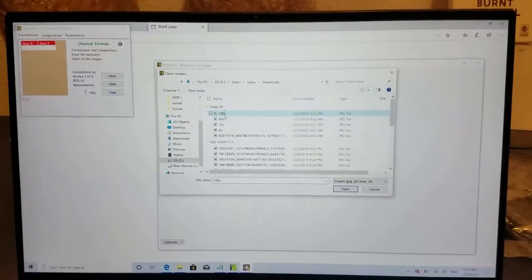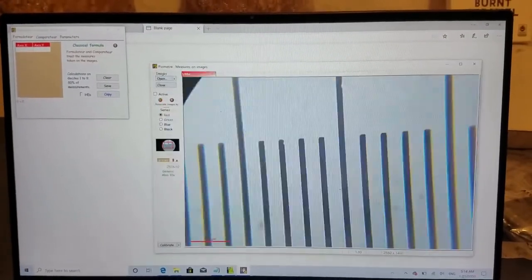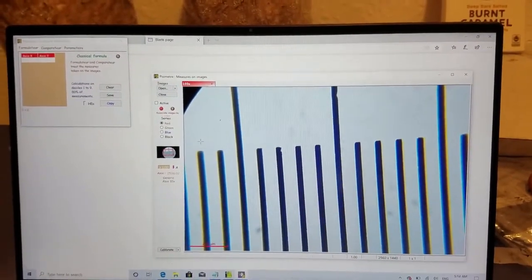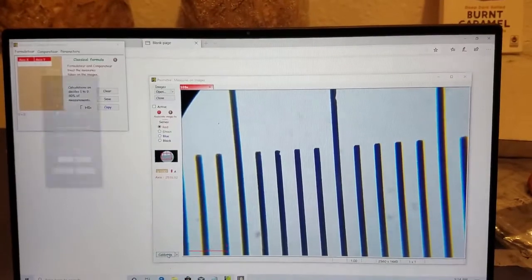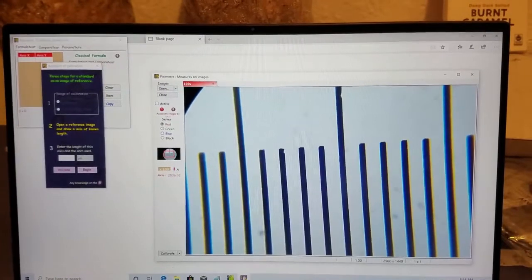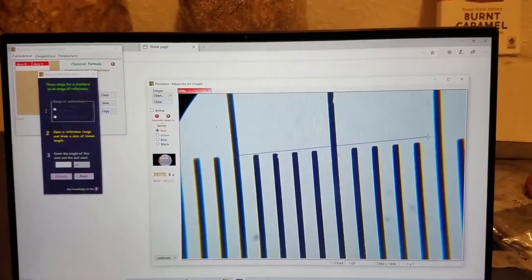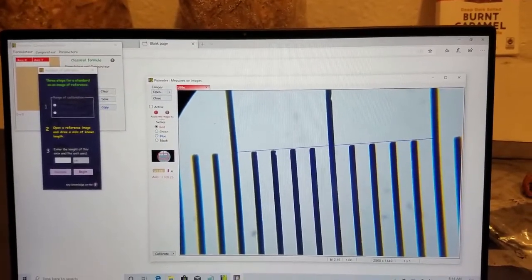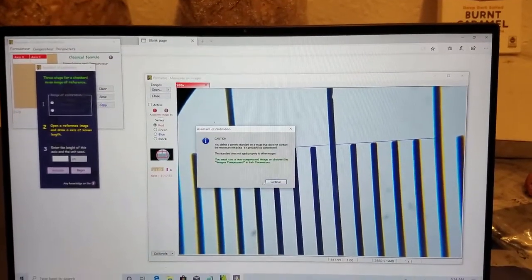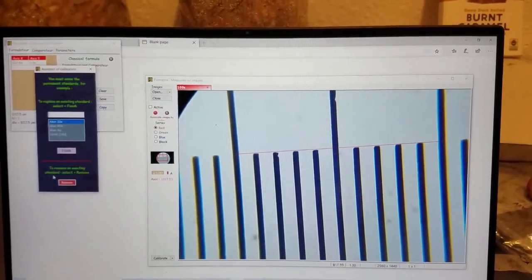So now we're going to calibrate Piximetre to be able to measure. And so this is the picture we took of the micrometer with the 100x objective. So these are 10 micrometer divisions. So we'll hit calibrate. And we select on all images. And so if we draw from here to here, that's 100 micrometers. So let's try to do it from the middle of the lines to be the most accurate. And now we tell it. That was 100. Hit validate.